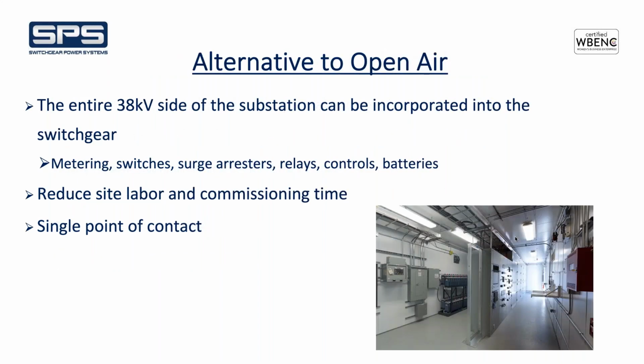So the first area we believe it can be applied is as an alternative to open air substations. The concept is we are able to take what would be the entire low side, the 38 kV side of the substation, and incorporate it into switchgear. I've touched on a couple of them, but it includes the metering, switches that you would have in the substation, surge arresters, obviously relays and controls, batteries.